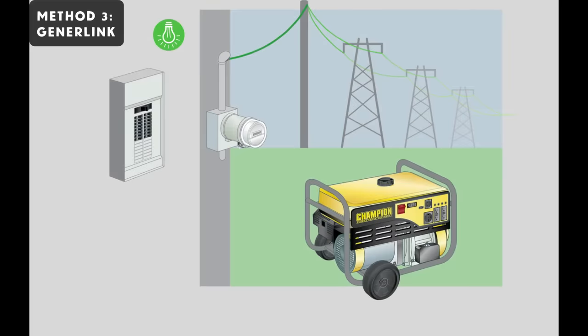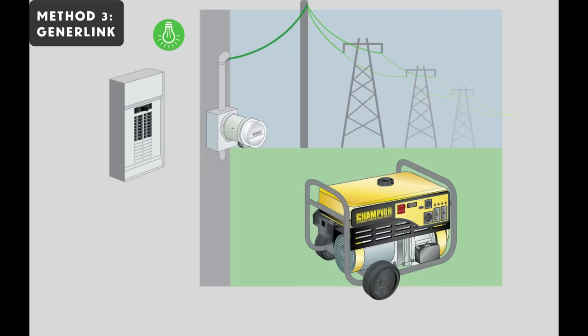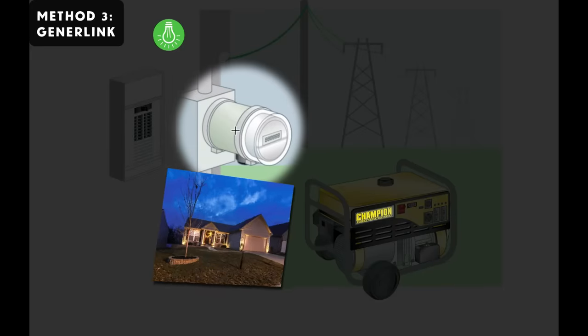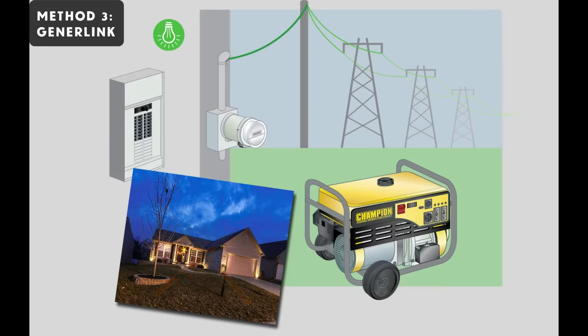And here's how it works. The GenerLink does a couple of things. First, right down here, there's a port that will accept a cable that connects the generator to the GenerLink. And you'll see that happening in a minute. Now, also, inside this cylinder, there are some pretty sophisticated things going on. The first of which is that the system can recognize whether the grid power is on or off. When the grid power is on, you're free to hook up the generator with the cable and start up the engine. But if the grid power is on, the GenerLink's not going to let power get past this point right about here. It's not going to go to your house, and it's definitely not going to back feed through the electrical grid, which is the main concern. That's the main idea behind all of these safe, legal connection methods.